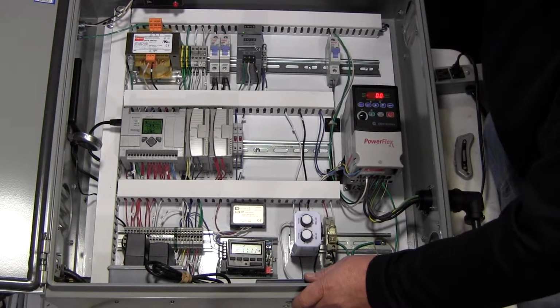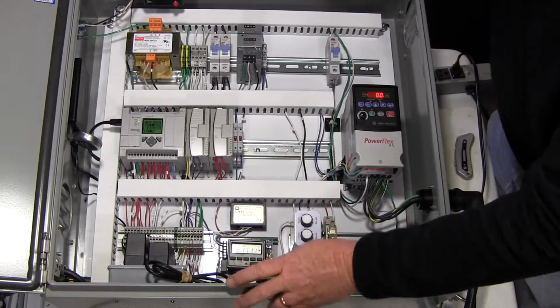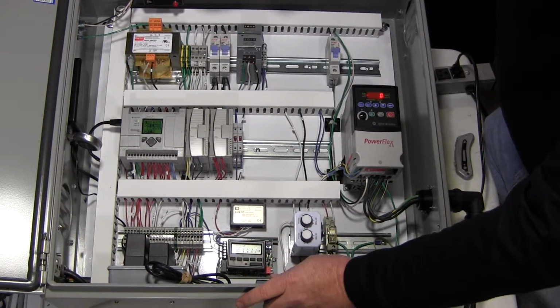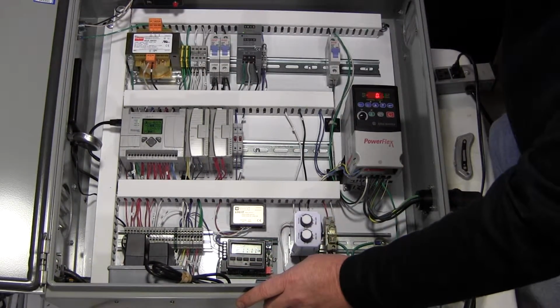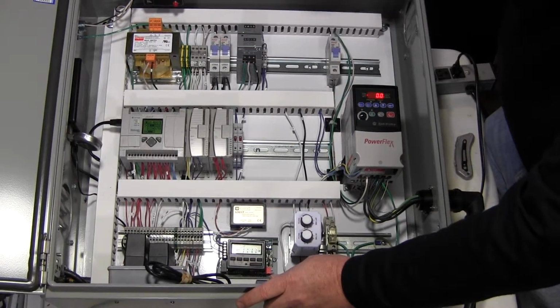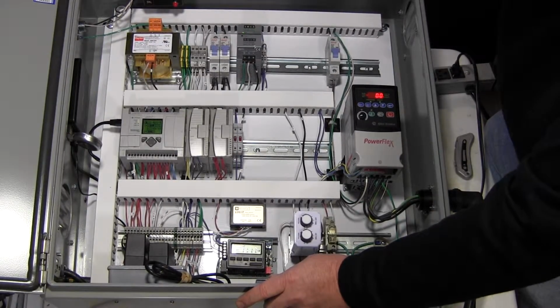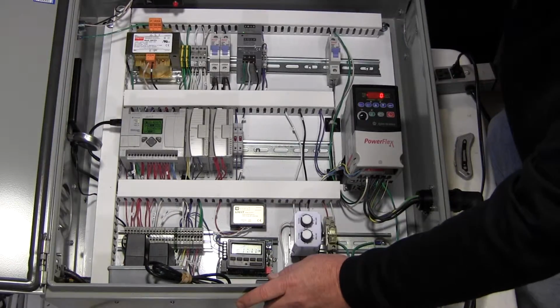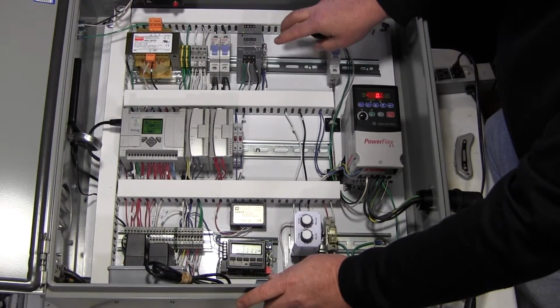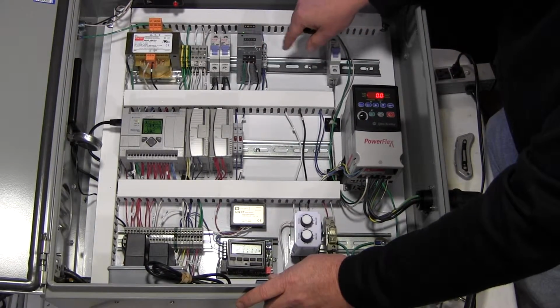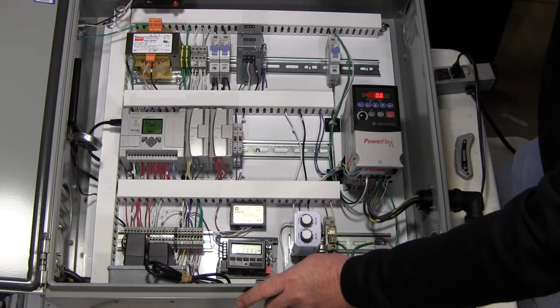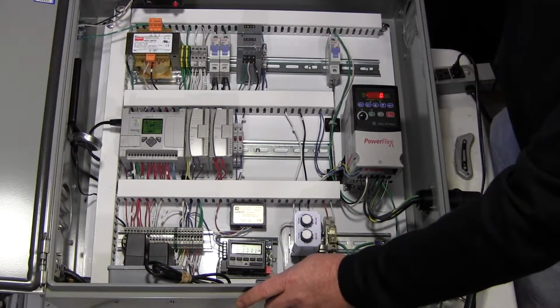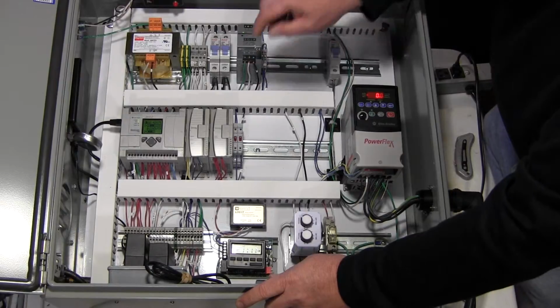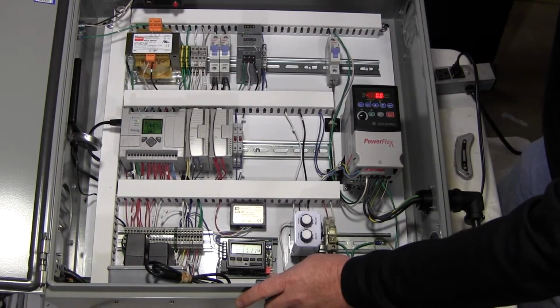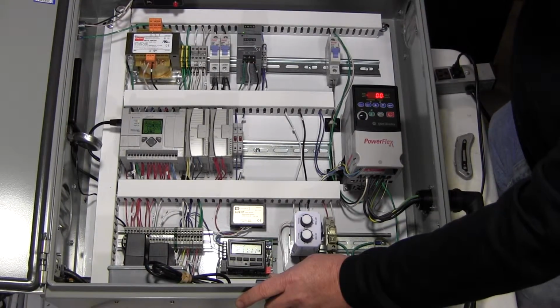That about covers it. You can see there's a ground wire on the transformer, surge suppression unit. We could use some contacts off that surge suppression to tell whether it's bad or not and send it back into this controller. If the DC power supply was a larger one, sometimes there are some output contacts on the DC power supply to tell that it's current limiting or isn't working anymore. You could feed that back into the microcontroller to say that there's some problems.